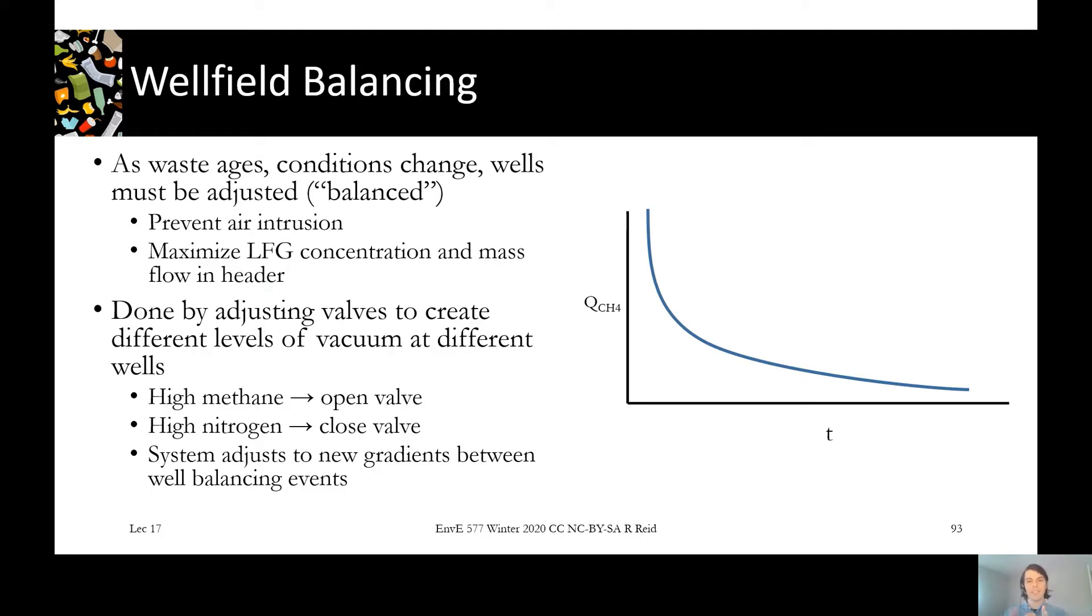So the landfill gas collection system has to be operated to account for this change in the gas over time. And this is done through what's called wellfield balancing, which is a process of adjusting the flow and vacuum in our individual wells to match the instantaneous gas production from that area of the landfill. So some wells will be in older areas of the landfill, some wells will be in newer areas and they'll all need to be adjusted to fit the gas production where they are and then changed over time as that specific area of waste gets older.